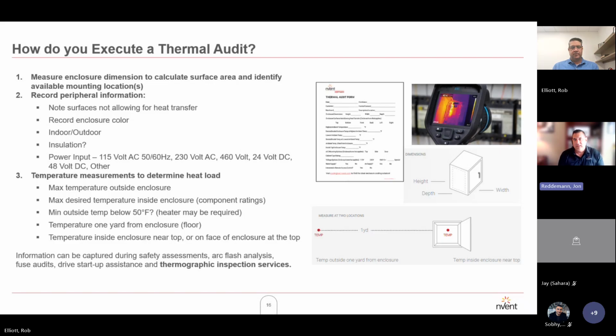So for example, on a day like today, down here in Arizona, it's 96 degrees. So let's just say it's 100 degrees in the facility, but as soon as I open the panel and measure the temperature at the top middle of the panel, I'm measuring 115 degrees. I have a 15-degree hotter temperature inside my panel than I do ambient temperature. I can plug that information into my selection calculator, and it will tell me how much heat is being produced to create that 15-degree delta, right?